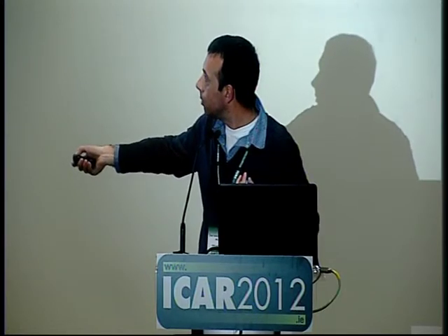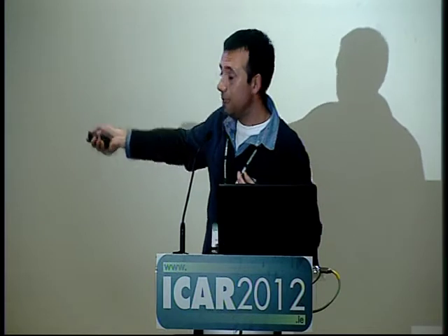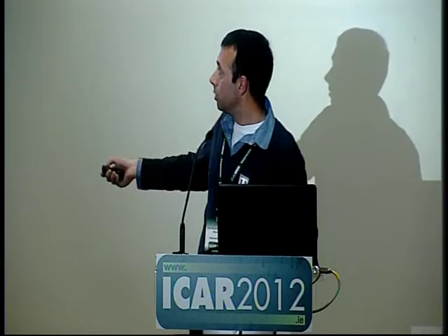Here you have a few laboratories from France, from Germany, from I don't know where, and you can see that most of the instruments are FOSS, but you also have some Bentley instruments and some Delta instruments. Here I represent the results in terms of the slope, between the prediction done by the master and the prediction done by each of the slaves. As you can see, in red is the prediction before the transformation, and in blue the slope of the prediction after standardization. In all the cases, the slope, of course, decreases. So it means that the slave and the master are almost the same.